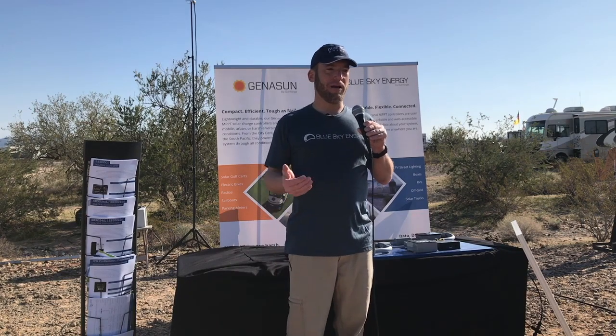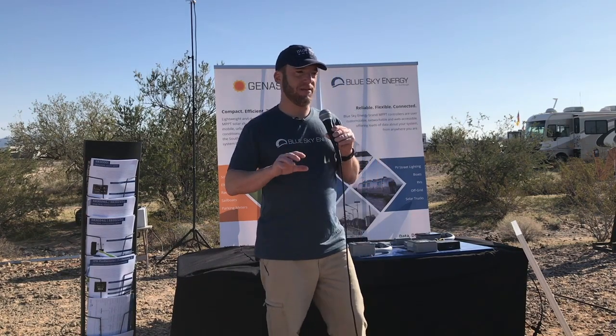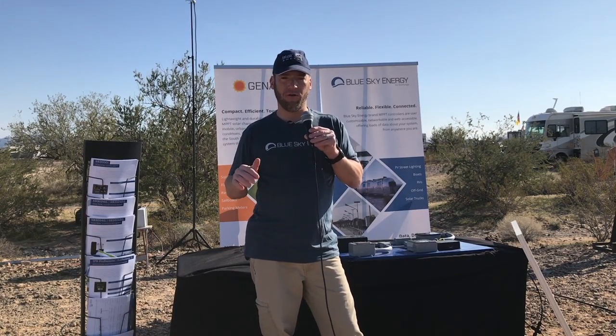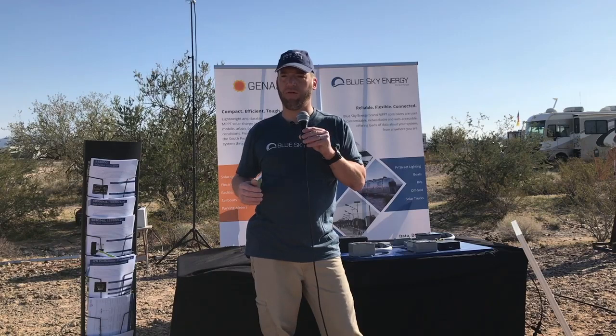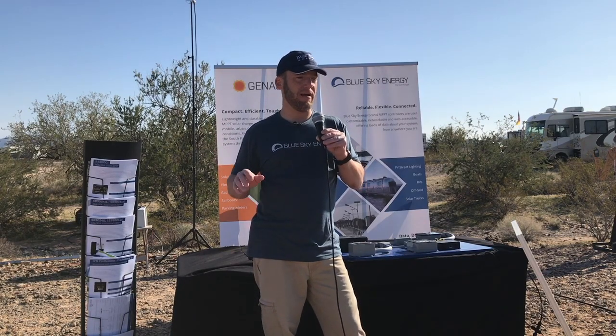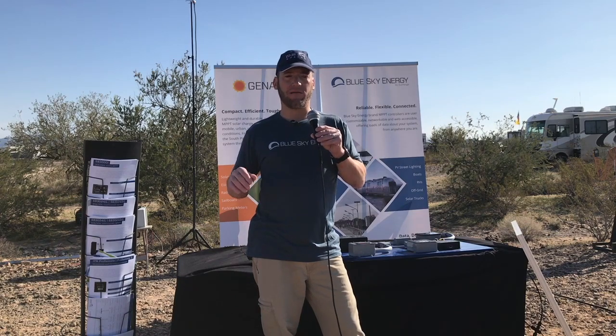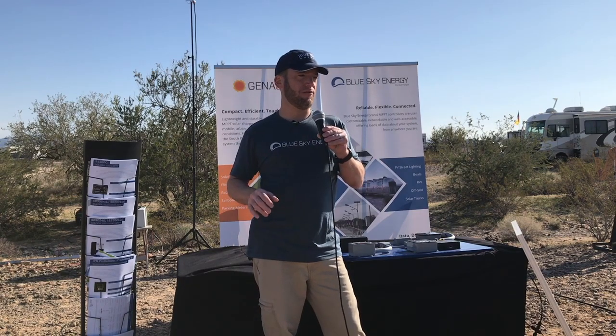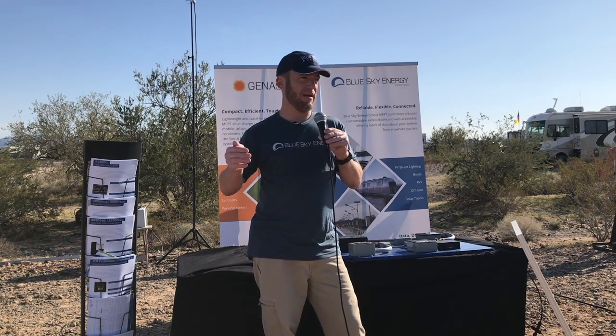More importantly, when you look at your standard profile versus lithium, the float voltage on a lithium battery is going to be much higher if you do decide to go with a multi-stage charge profile. It's going to be about 13.6 if you're cycling your batteries every day-ish, and about 13.4 if you're basically going to let them sit for weeks on end in between.